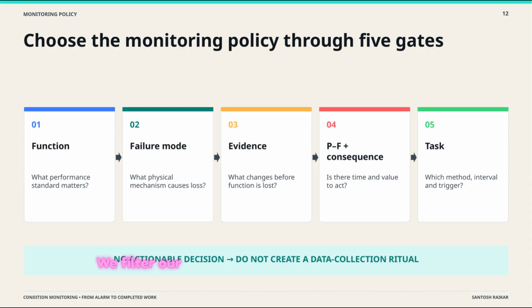We filter our monitoring policy through 5 gates: function, failure mode, evidence, P-F interval, and finally the task. If you reach a point where there is no actionable decision possible, stop. Don't create a data collection ritual just for the sake of having numbers in a database. Data without a potential action is just overhead.